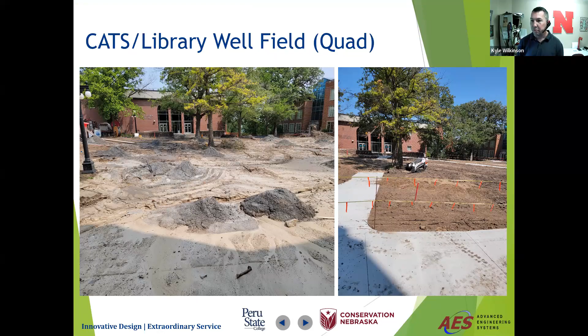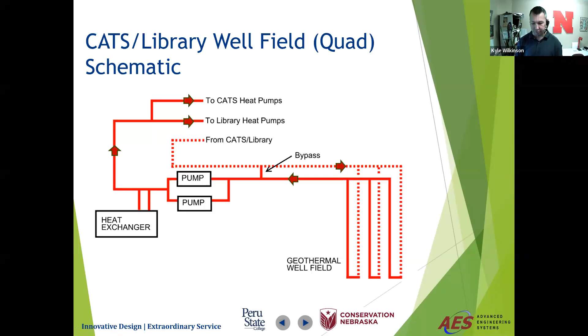Here's a quick schematic of how it works. We'll call the solid line the supply, so whether that's cooled or heated water, it comes in and the pumps pump it. You can have an auxiliary heat exchanger, and they have a few of those down there to heat the water just in case. That water comes up, gets pumped, and goes to the heat pumps, which use it to heat or cool. The return water, shown in the dash, goes back. A lot of times we design in a bypass, because if our ground is roughly 55 degrees and our water is around 50 to 60 degrees, you're not going to get a whole lot of temperature gain by sending it out. So we'll open up a bypass right here, which saves some pump energy. Generally the pumps are on variable speed drives, so they can change speed and save energy as they slow down.